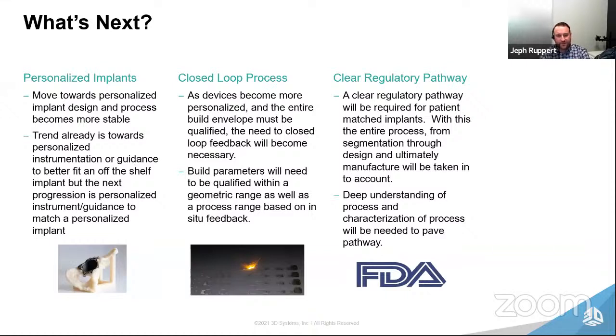Then we start thinking about closed loop processes. When you're building within an envelope rather than building the exact same size, what does that validation and verification look like? Closed loop processes, both from the simulation side through to in-process changes within a validated process window, will allow us to build personalized implants with better reliability. Build parameters will still need to be qualified within a geometric range and within that process window, but this will allow for higher yields, better safety and reliability of those implants.